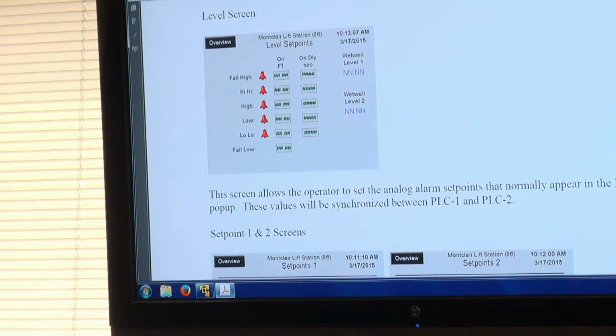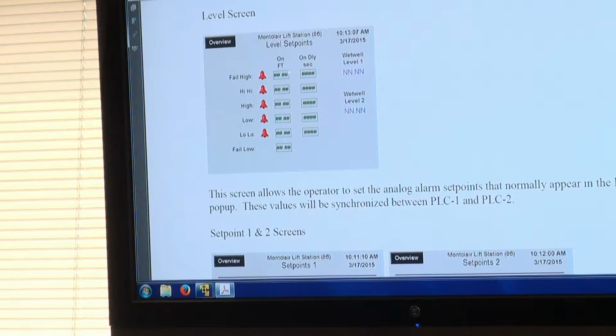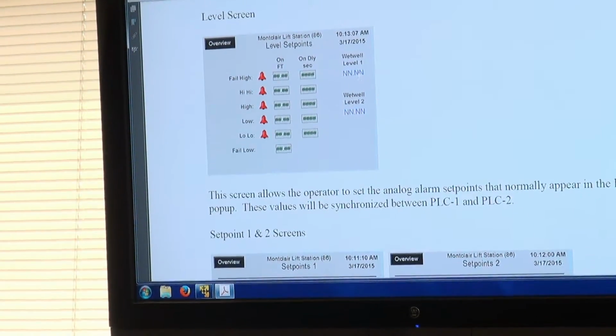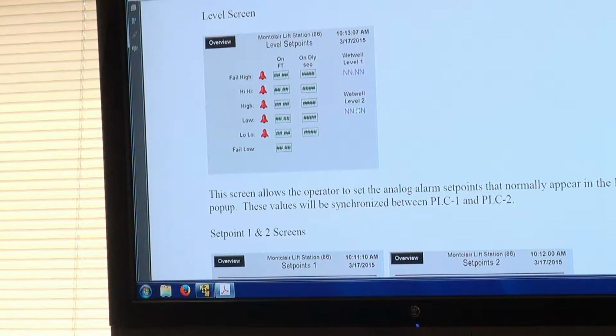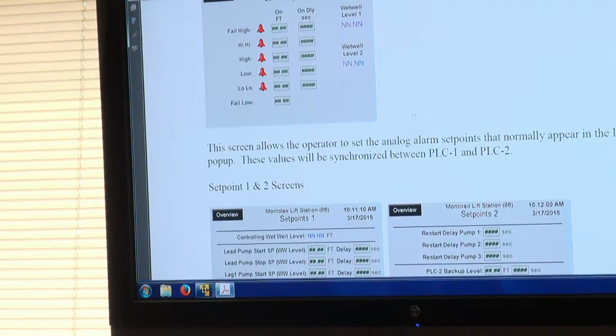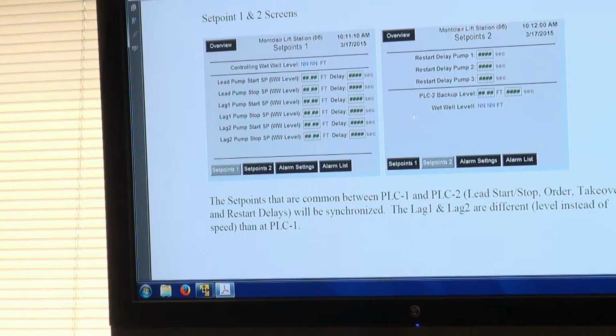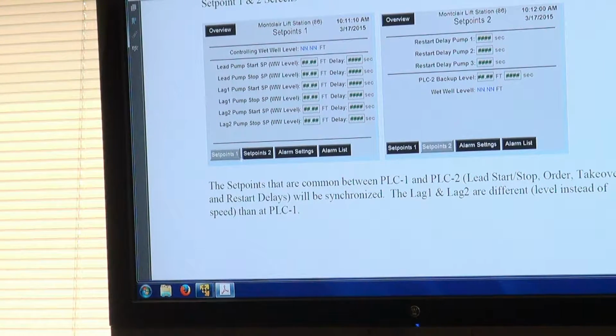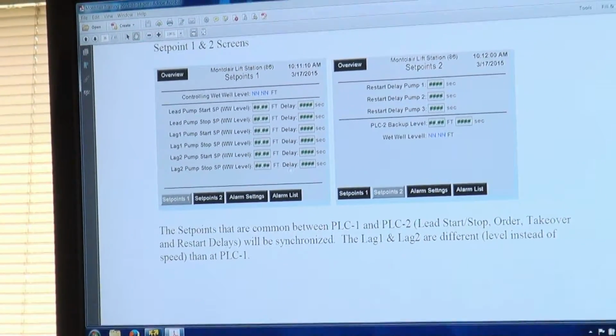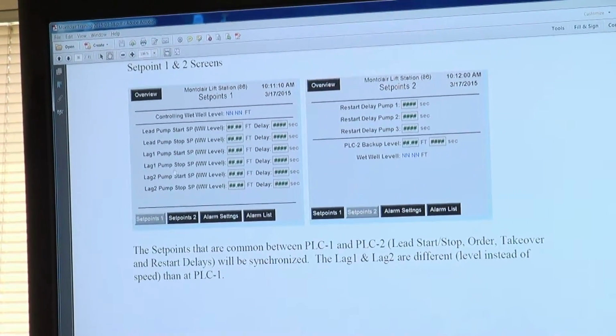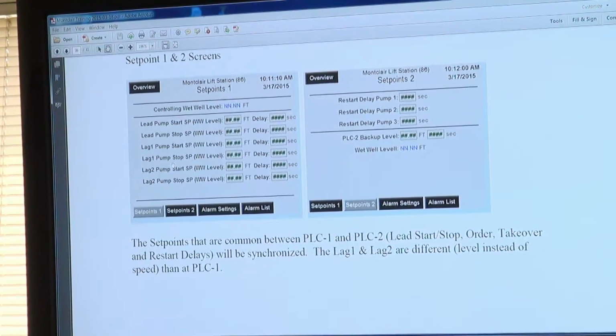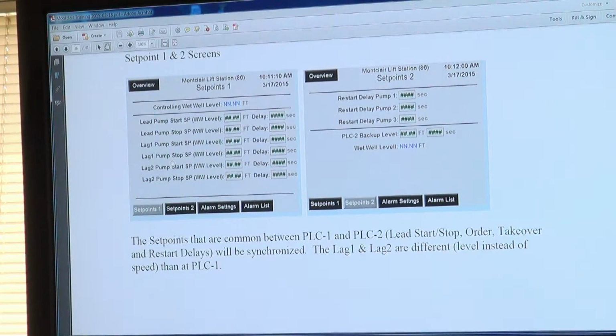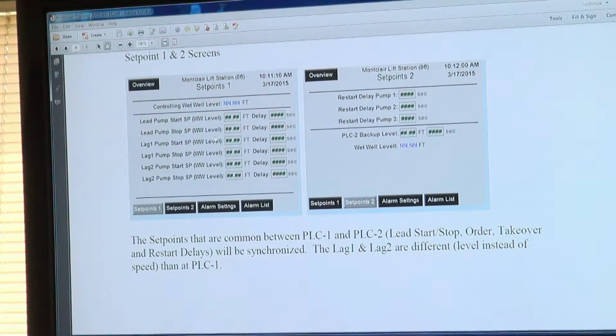When you press the level, it pops to this one where you have all your set points for the level, here's your delays, and then here's level 1 versus 2. It does not have a differential level alarm. At the bottom we have set points 1 and 2 that you could press. Set point 1, and we actually start based on level, not based on pump speed at PLC 2.